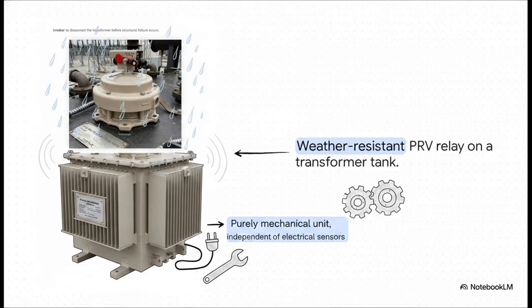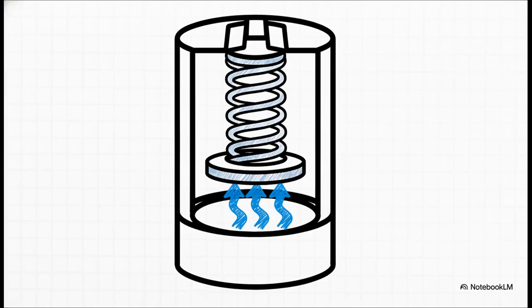It's a purely mechanical unit sitting right there on the wall, completely independent of any complex electrical sensors. And inside that housing, it relies on just 4 essential mechanical components working in perfect harmony. The star of the show is the pressure-sensing piston. Think of it as a mechanical transducer. It converts that dangerous fluid oil pressure into physical movement upward, pushing against a precisely calibrated steel spring.